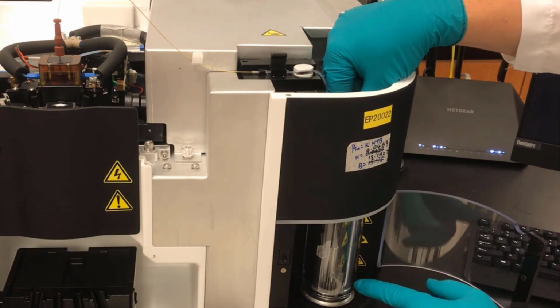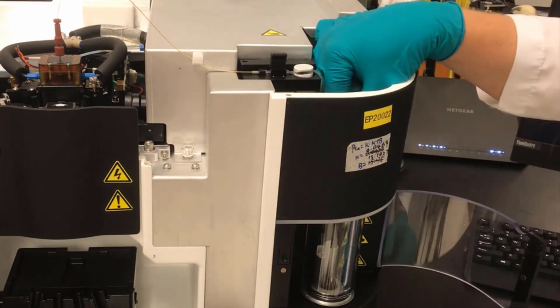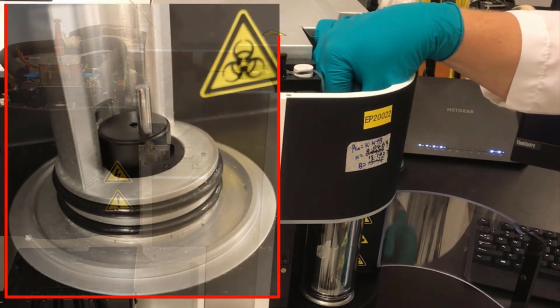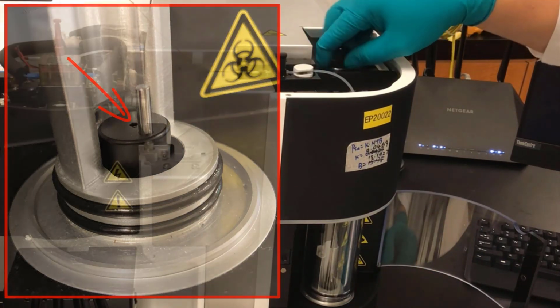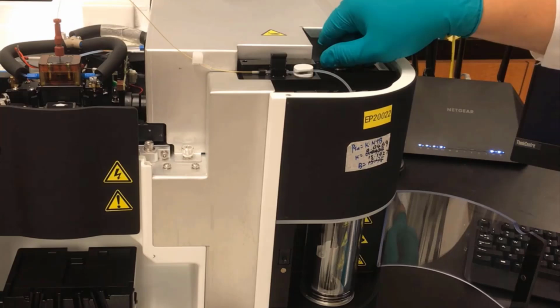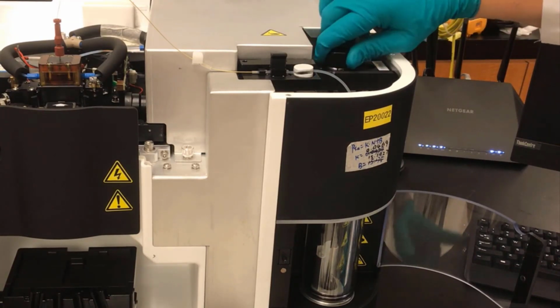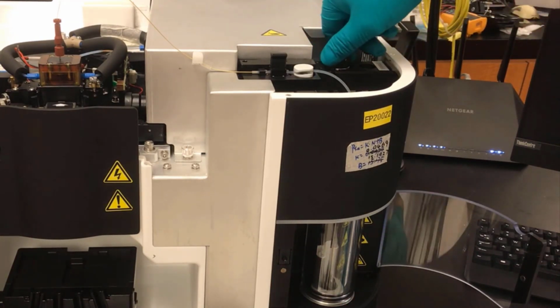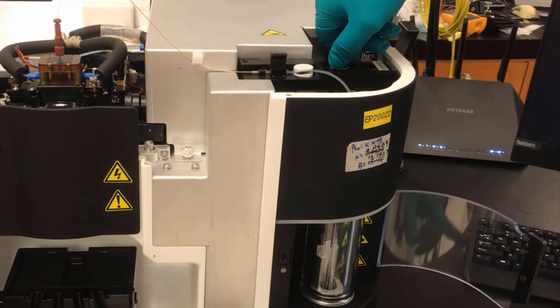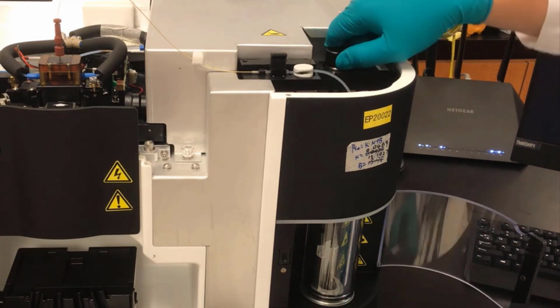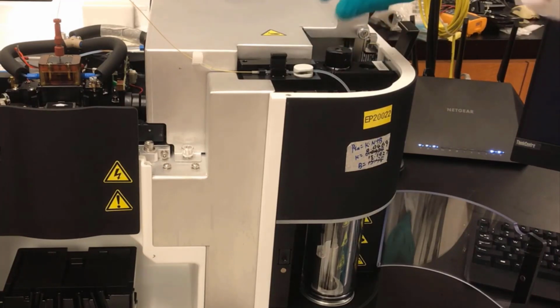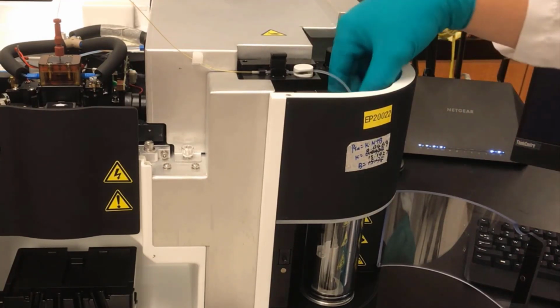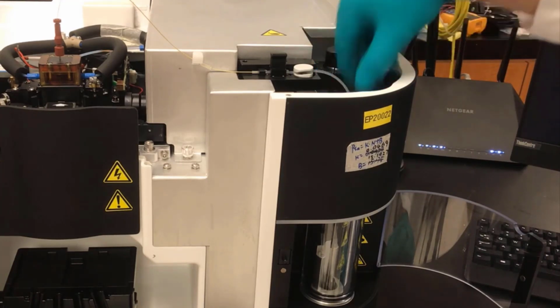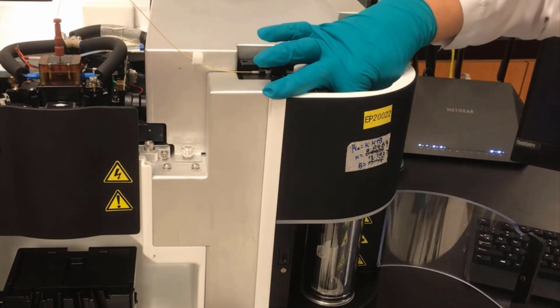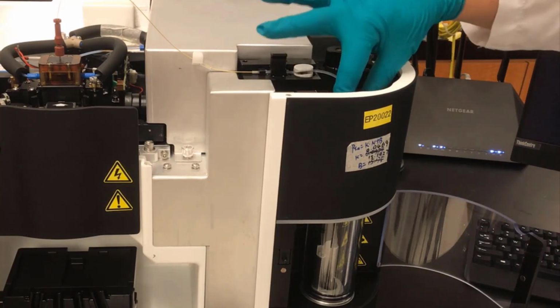Move the probe up and down to make sure that it is hitting the bottom of the sample gauge. You can see here that the probe is hitting the bottom of the sample gauge. At this time, tighten the fitting until you hear a click. Rotate the black thumb screw clockwise to move the chamber until the sample probe is slightly above the sample gauge. Then, slowly move the chamber up and down to make sure that the probe is not crashing the edge of the sample gauge. Repeat this process until the alignment is correct.